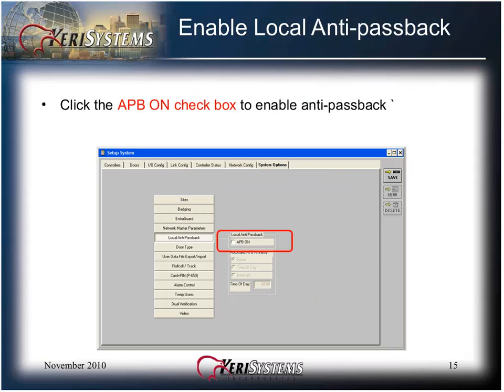Click the APB On checkbox to enable anti-passback. Anti-passback prevents someone from accessing a secure door and then passing his or her card back to someone else to use, or from holding the door for others to enter the area. This is done by implementing rules on how often cards can be presented to readers. Local anti-passback is described in detail in its own training module.